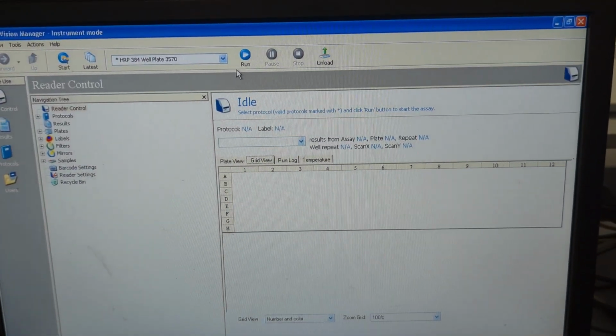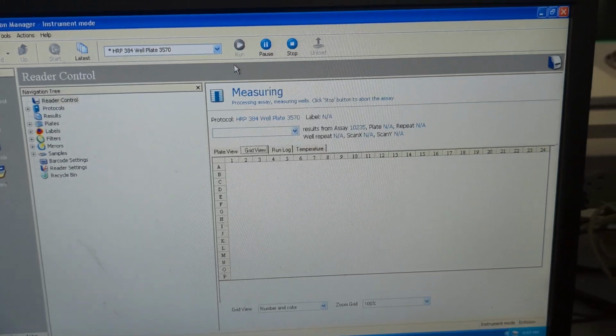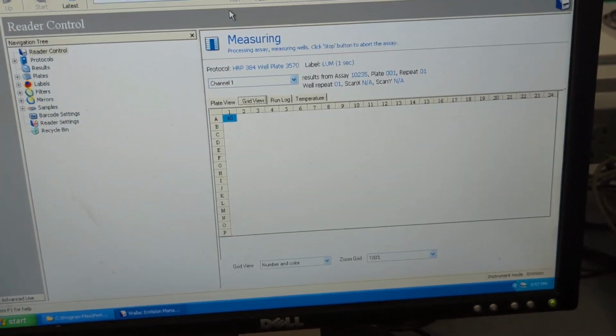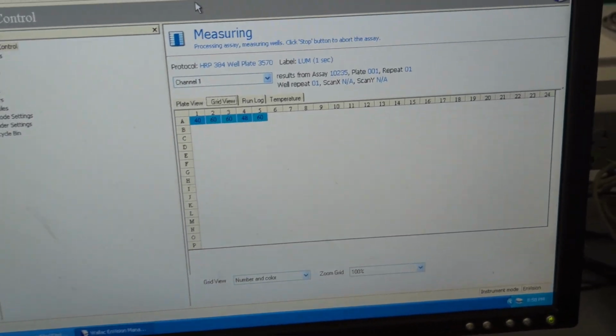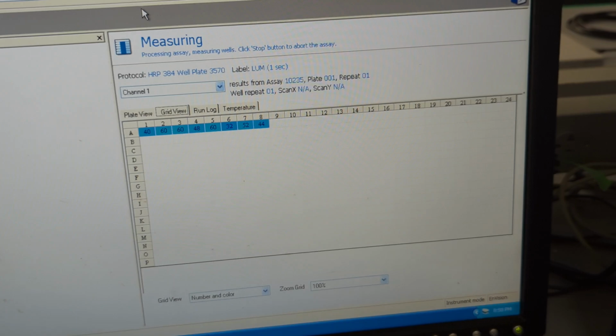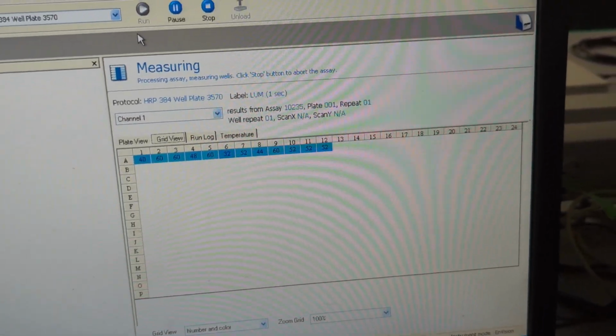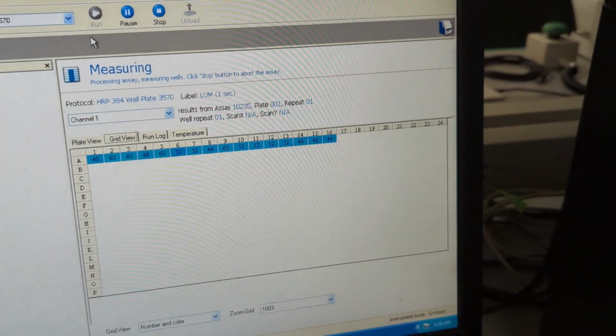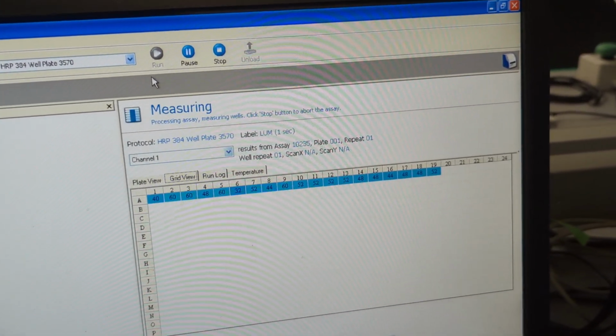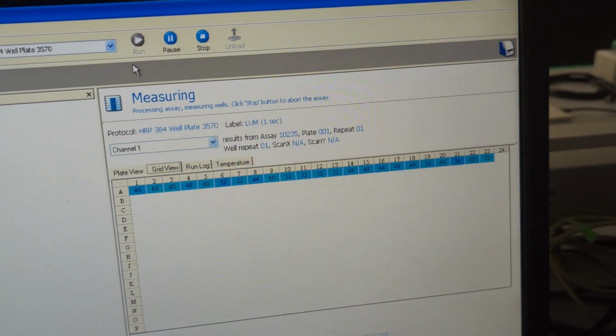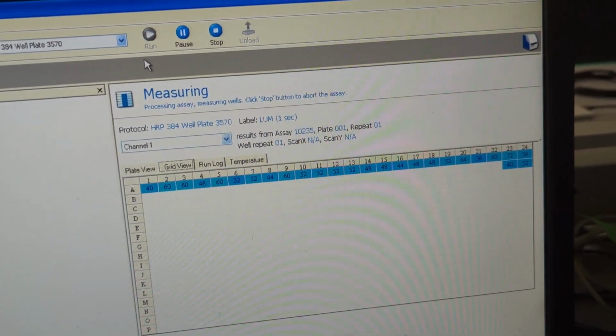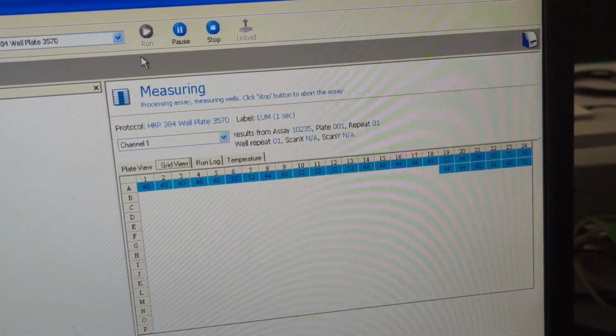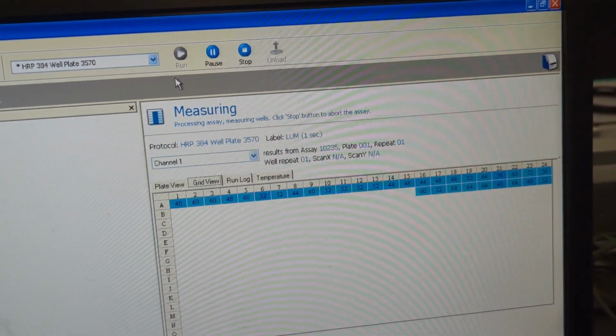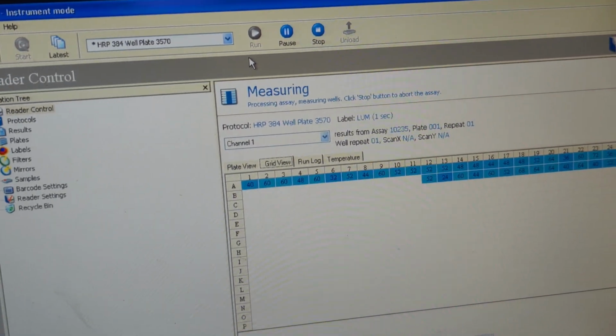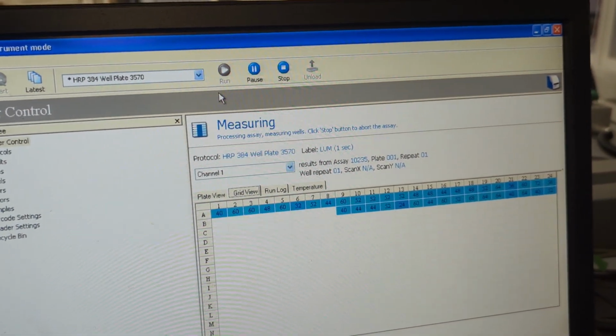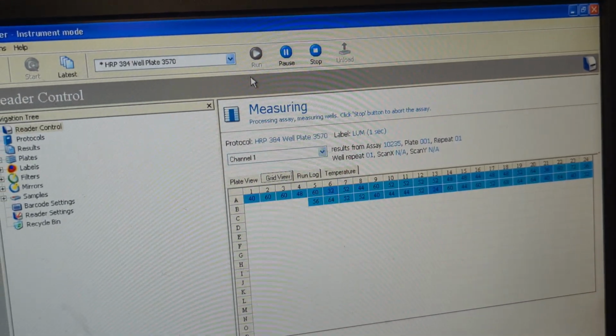All right, so now I'm just going to run a quick dummy test, with a blank plate, to make sure that the instrument is able to complete an experiment. And this is actually the same experiment that the end user was running when they had their issue. So I like to try to duplicate that as much as I can, just to make sure everything is good. Again, the basic mover tests, the random loop tests for the X and Y motors, completed without any errors. And the thing is, I was able to recreate this error prior to lubricating the linear ball bearing rails and doing some of the service mode tests. So I definitely saw it, but it's looking good so far.